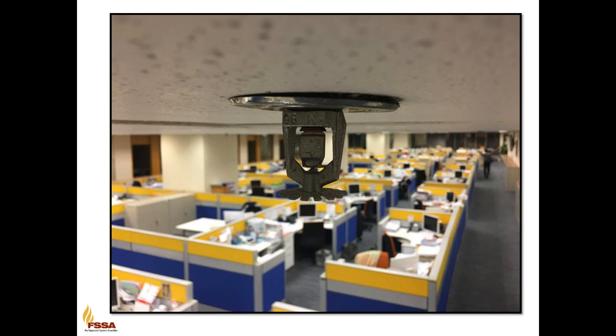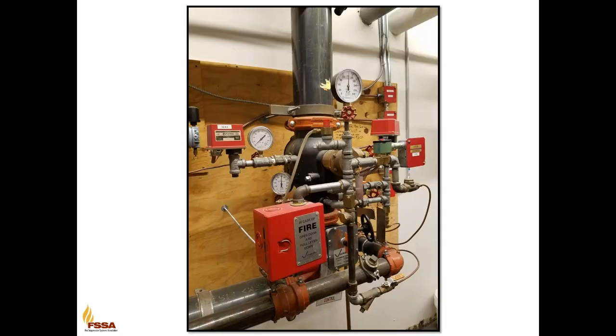To address this, the industry developed a way to keep the pipes overhead filled with air but still maintain the same level of protection. This is called a pre-action sprinkler system. It is designed to be activated by a combination of smoke and heat. To do this, a section of the sprinkler piping is isolated and controlled by its own separate valve. In a normal state, the piping above the critical area is pressurized with air to avoid any possibility of a water leak. When the system smoke detectors activate, the control valve opens and the pipe fills with water.